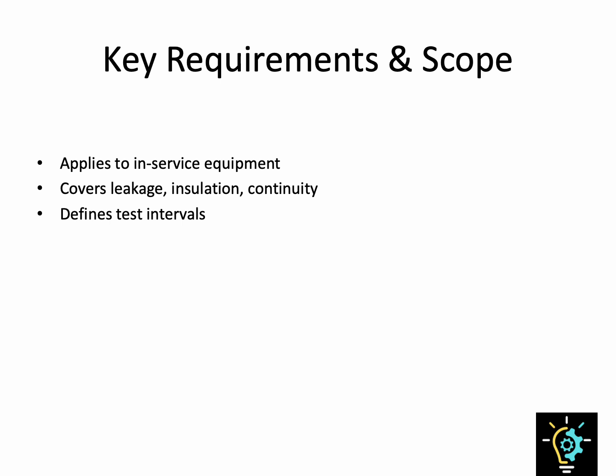Another major part of the scope is frequency. So if you've read the 2014 edition, it suggests following the manufacturer's recommendations, but if those aren't available, a risk-based interval of 6 to 36 months is recommended, depending on the device's use, environment, and risk profile. Overall, the scope is very broad, and it's enough to cover most of the equipment, but flexible enough to be applied consistently across different healthcare contexts.